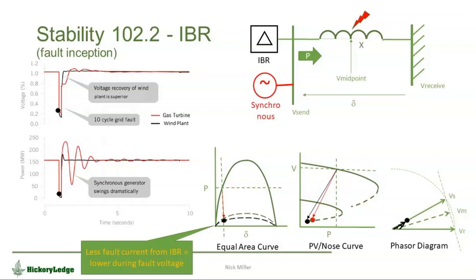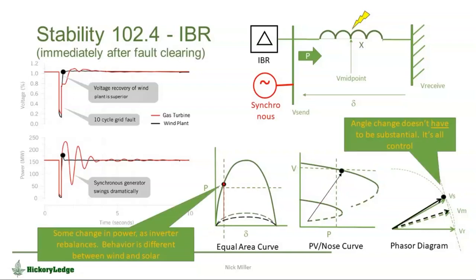But because it's inverter-based, we do not need to worry about the power. What happens to the energy during the fault? The energy during the fault in the PV curve, in the case of photovoltaics, just goes away. In the case of a wind turbine, it goes into accelerating the wind turbine. The wind turbine speeds up, but that doesn't mean that its angle pulls apart like the synchronous machine. So when we clear in this figure, we are now not particularly farther out on the PV curve. And if the phase lock loop has not gotten confused about where it is, the angle hasn't changed substantively and the power is very similar. So we're at a really radically different place that's quite a bit friendlier at the end of the fault.